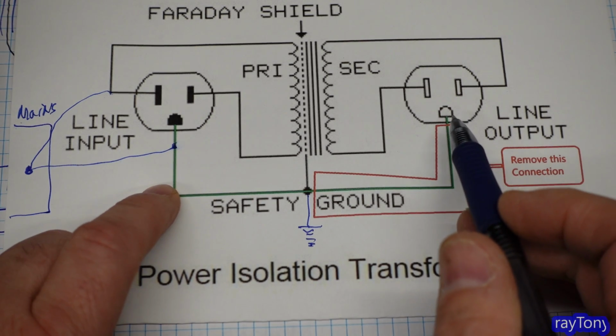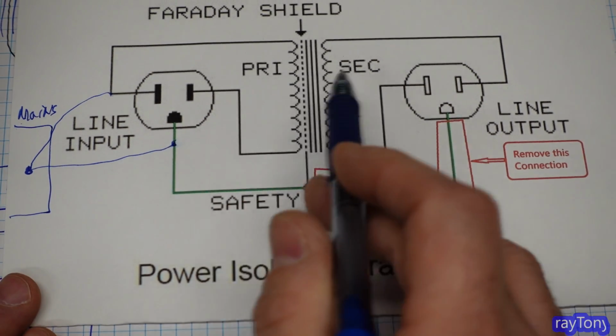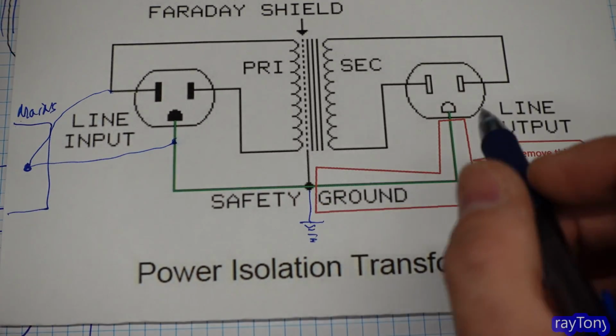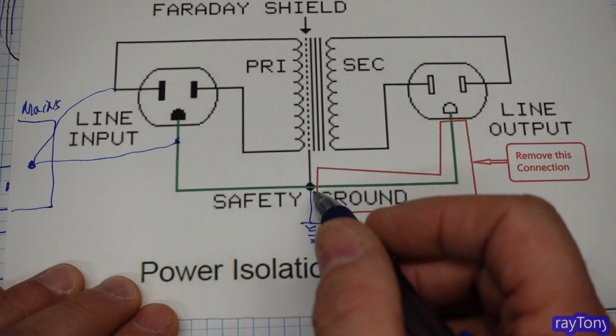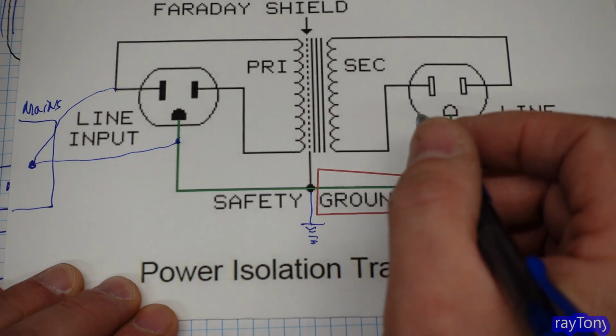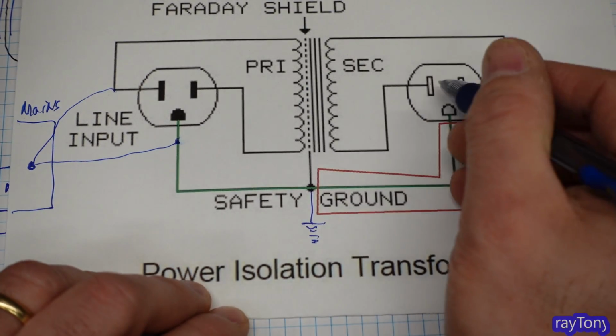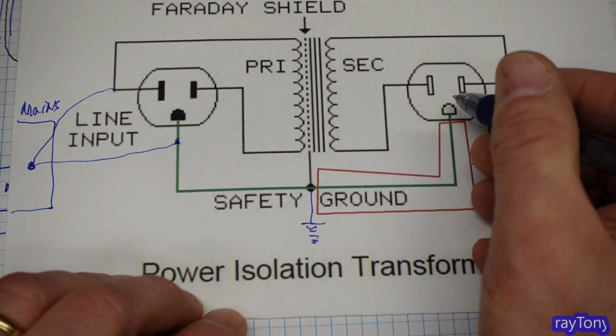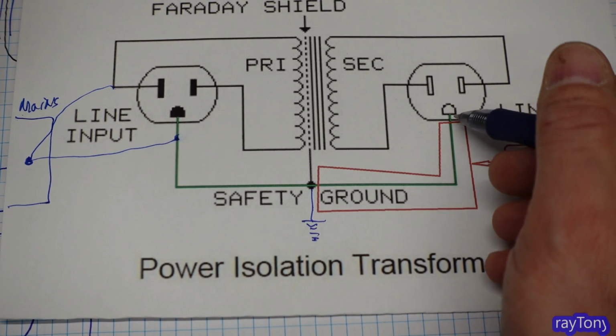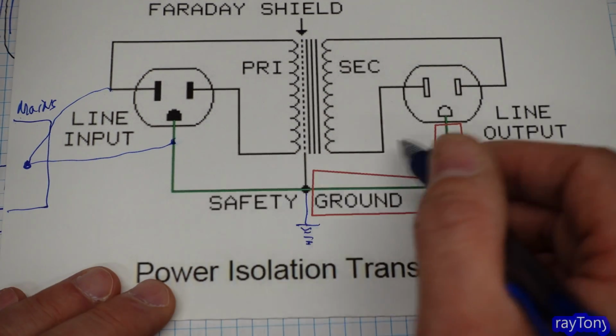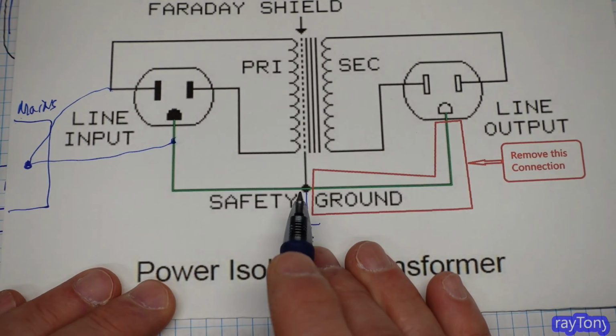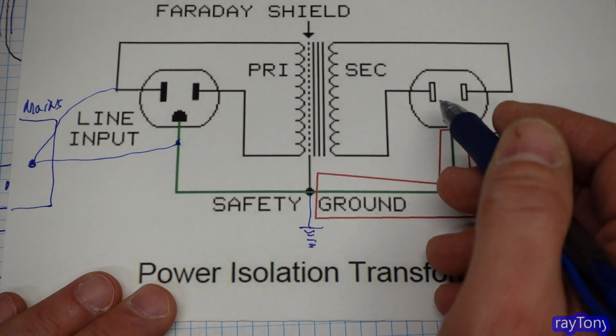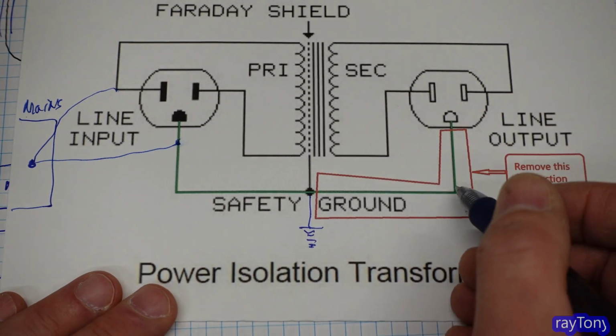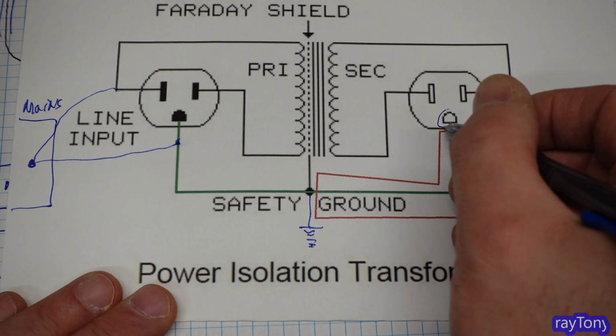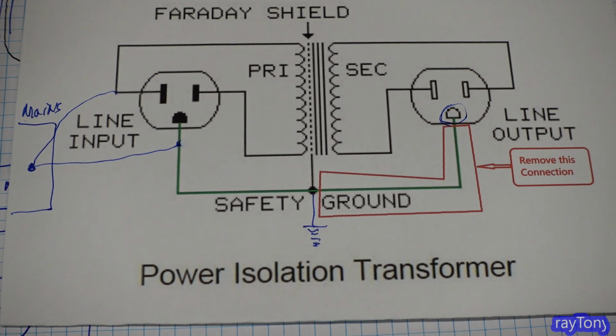They kind of defeat the whole purpose of what we're trying to do. While this does give electrical isolation here to here, this ground lead is now tied into here. If you only plug into these two pins, you have electrical isolation, but if you plug in something with a 3-prong plug, you've just taken your isolation out of the equation. So typically, a modification you'd make when you buy these would be to remove this portion of the ground wire so it's a no-connection.